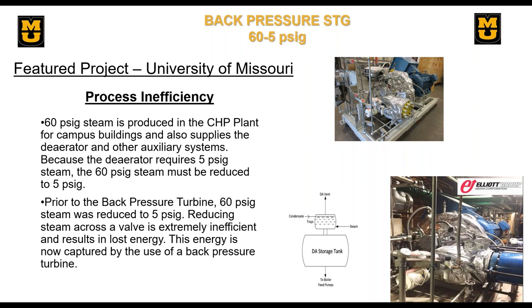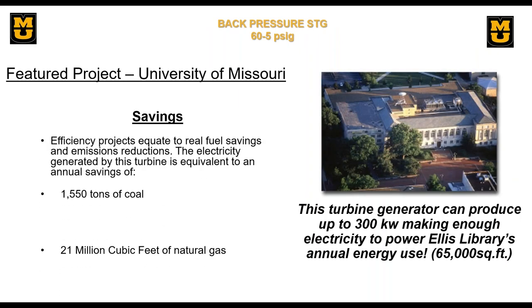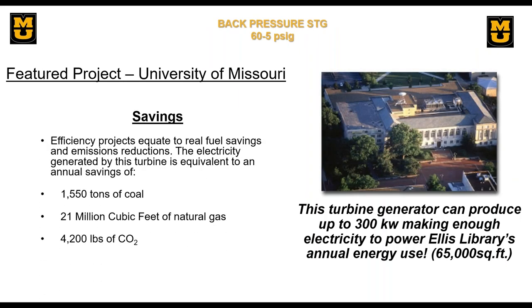So what they ended up doing, go to the next slide, Patrick. The amount of steam that they had available was enough to produce about 300 kilowatts. So they installed this back pressure turbine. I believe it was late 2017, and it has been operating since about that time. Since then, they've identified real fuel savings and emissions reduction. You can see the various numbers here that they provided, based on this small turbine generator, and what it's really doing for them.